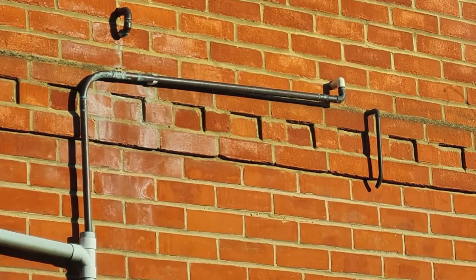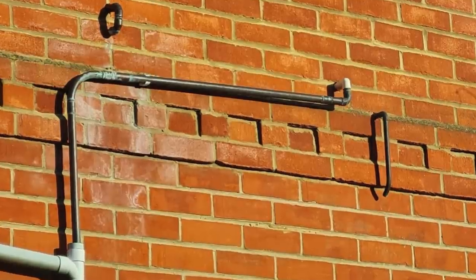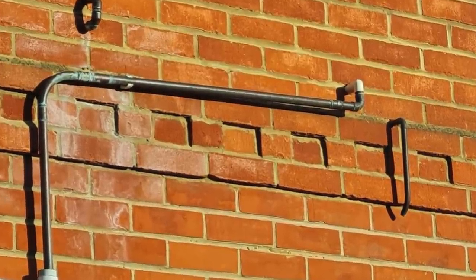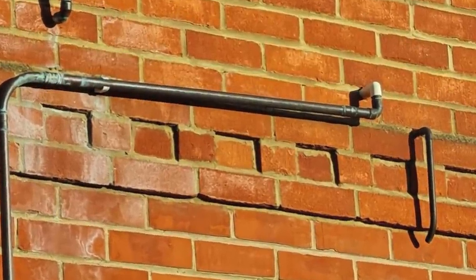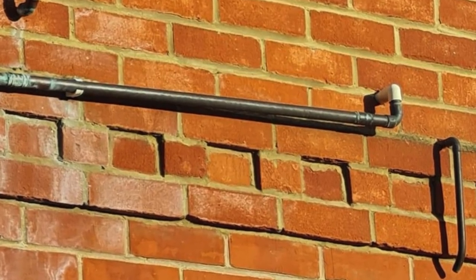So what material can we have this condensate pipe made of? Well, I've said it's got to be plastic, and we use overflow pipe internally, and it has to be standard waste pipe, could be outside. We cannot use copper pipe, and we cannot use steel pipe for a condensing pipe because it completely rots away.